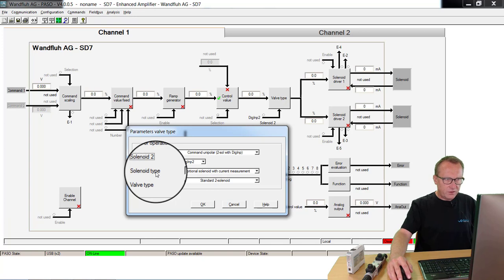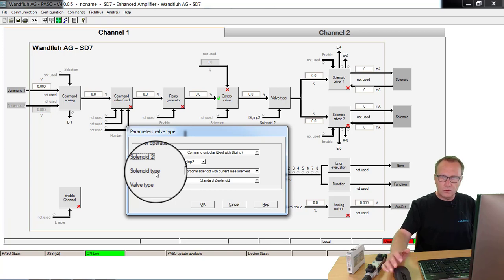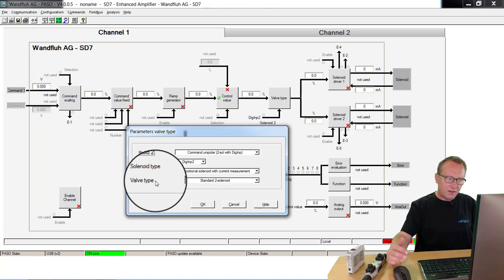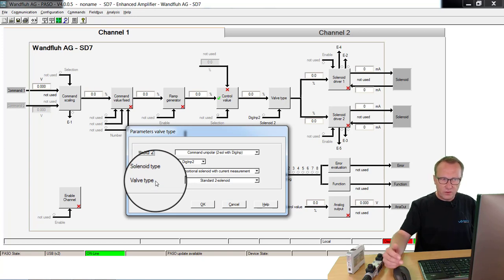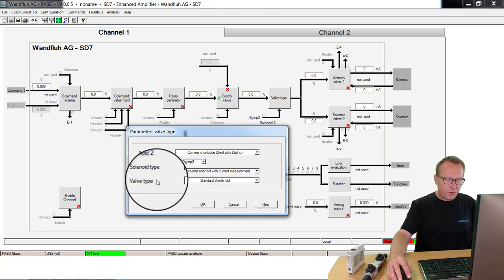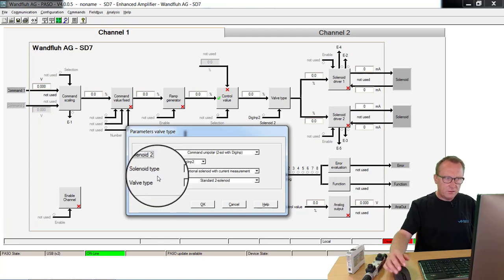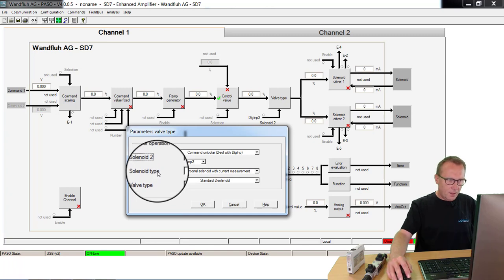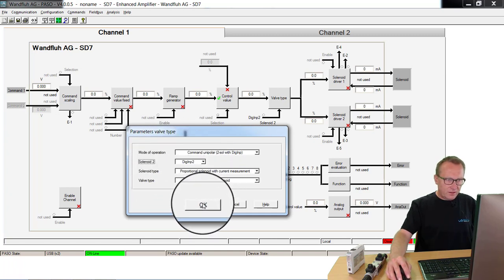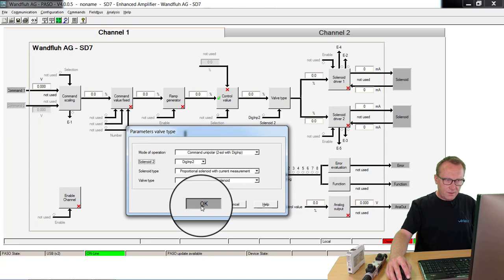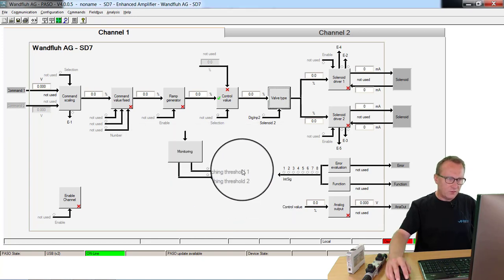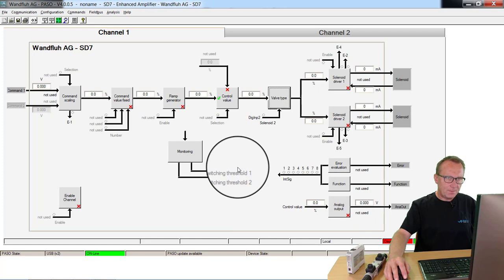The two other parameters we leave on default value. With the solenoid type, you can switch on or off the current measuring. With the valve type, you can select if you are working with a special 4/3-way proportional valve. Because on our demo application everything is standard, we leave this on the default values. If everything is correct, I click to the OK button that these values really will also stored on the electronic device.